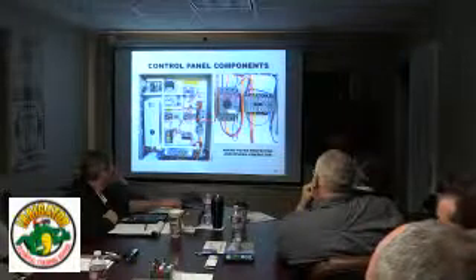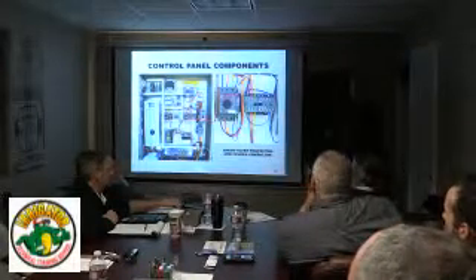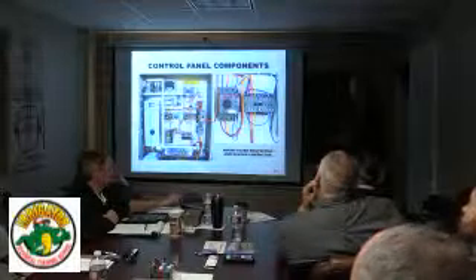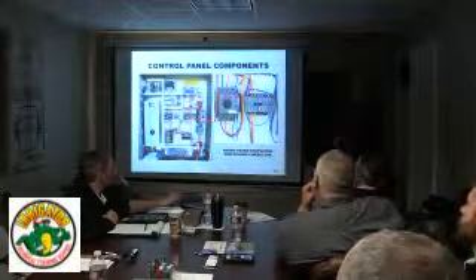Yeah, this is a forward reverse contactor for the Amiad. We'll look at the Amiad filter in a little more detail, but when it does a flush cycle, it travels forward and then in reverse, and you'll see what I mean when we look at that. And so that's why we have 2 of these interlocked, so we can make the motor go forward one time and reverse the next time.